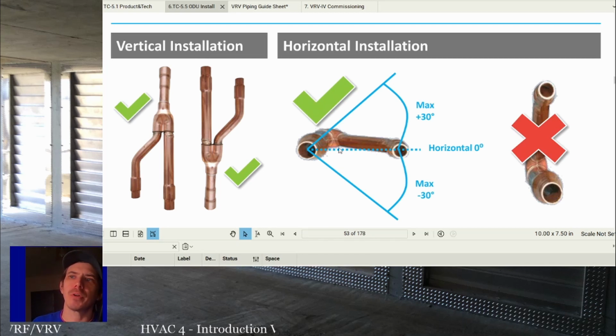How they generally recommend these Y kits are installed is on a horizontal. And you see how it says plus or minus 30 degrees? It's not really plus or minus 30 degrees. This thing should be dead level across for the most part, okay? The little bit out of level it should be is so that both these pipes can sit on the same piece of strut. So it can be a couple degrees out. Plus or minus 30 is technically okay, but it's not really okay. You want these Y kits to be horizontal.